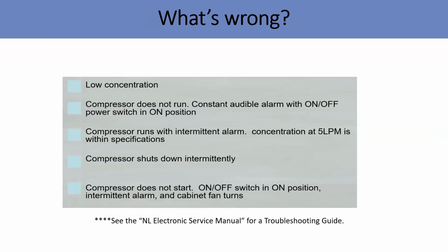So, troubleshooting. Normally, what problems are you going to find in your oxygen concentrator? Low concentration of oxygen. That's very common. The compressor doesn't run, or there is a constant alarm with the on-off power switch. When in the on position, you hear an alarm, but the compressor is not running. Low oxygen concentration can be caused by the sieve tank, or by high or low pressure, or sometimes leakage. Maybe the sieve tank itself has reached the end of its lifespan.